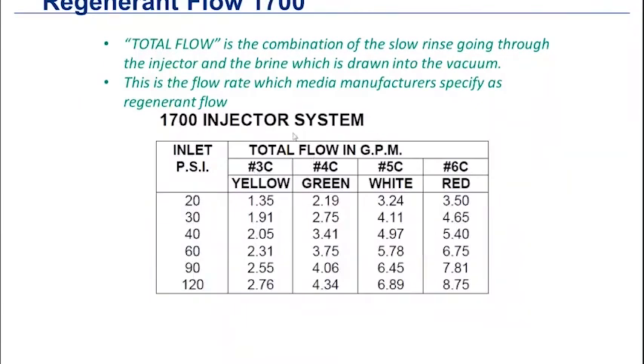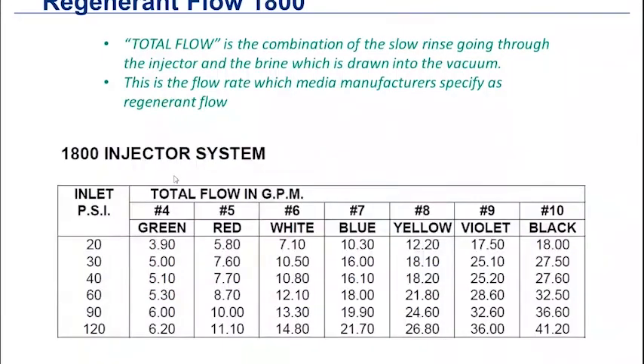For the 1700 injector series, the same issue applies — we're dealing with larger tanks that require more regenerant flow, based on how much media is in the tank and the tank size. If we drop too far below the range, we may need to go up in injector size. The bigger the tanks, the a little more wiggle room you have. Same thing with the 1800 injector series — same information applies; if you drop out of range, you may need to go up to the next injector based on water pressure.